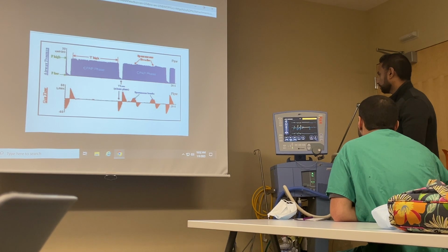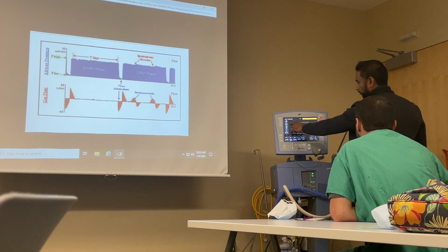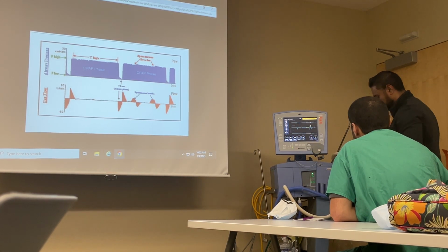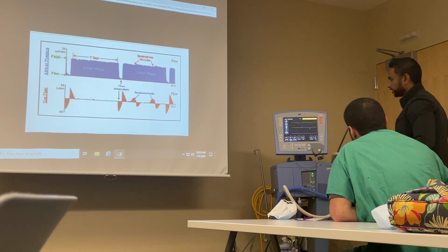See what I'm saying? Did you see that? The pressure stayed open at 20 and stayed that way. I was triggering my circuit, my test lung, and in that time frame the patient is breathing, and you can see the squiggly things, the waveforms, going like that. So watch this. Okay, inhalation, and now breathing, see?